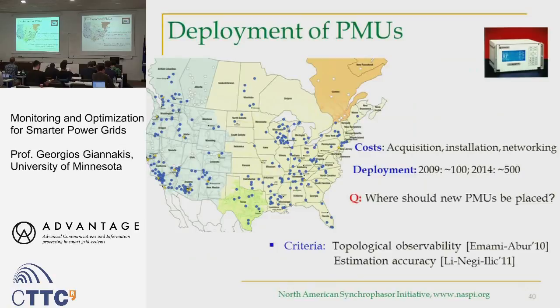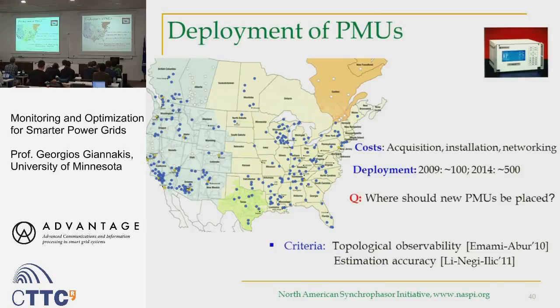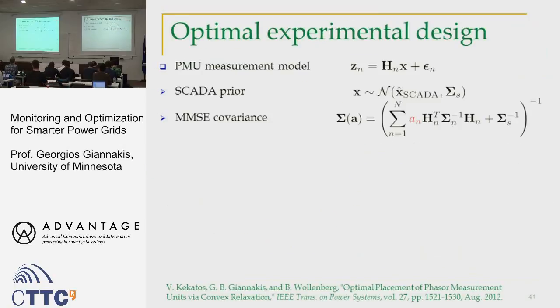The major costs in deploying PMUs — and about 100 are being deployed per year in the US — include acquisition and network installation. A major question is: if you have a choice, where do you put the PMU, since you cannot put them everywhere, at least in the near future? The criteria proposed are either topological observability or estimation accuracy, which are somewhat related.